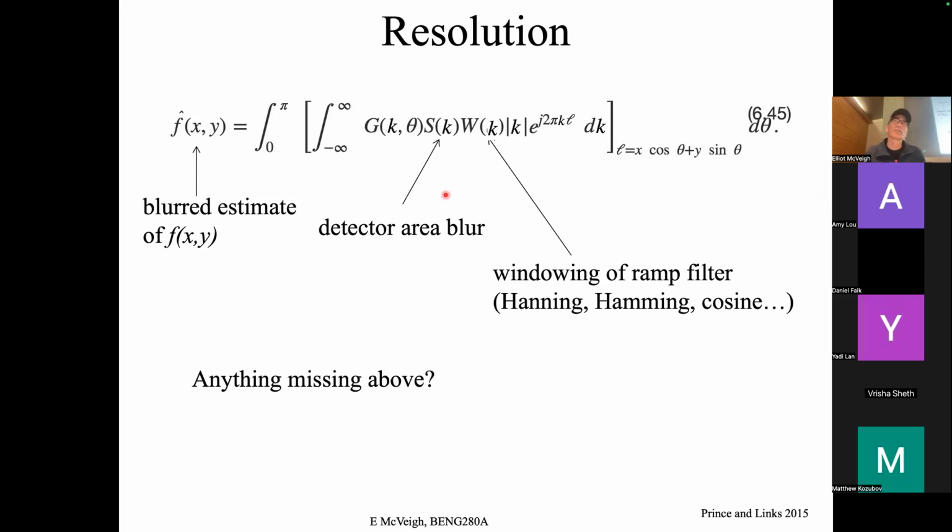This really only matters when you're looking at super high resolution stuff. If you're looking at a really tiny feature in the inner ear, like you can see all of the mechanics of the inner ear on CT, the little bones, the stirrup and everything, these little things. When you're trying to image something that's down at that size, you want a really small spot size. When you're trying to image somebody for cancer in their liver, it's not as important.